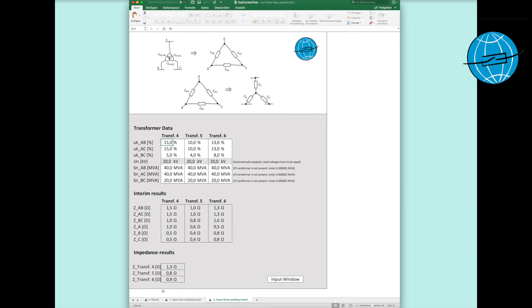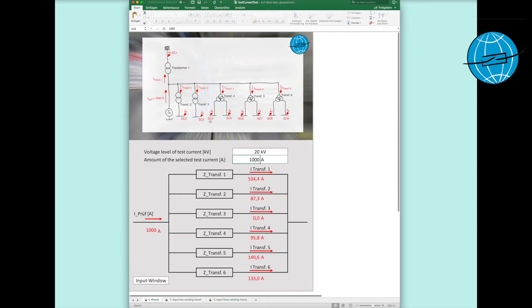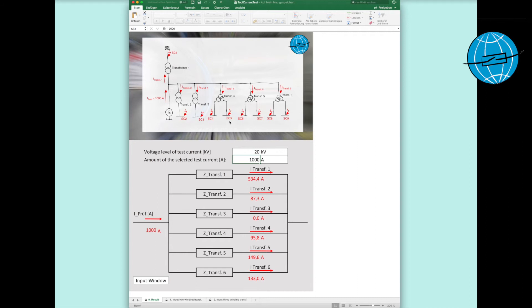In addition, everyone can now convert the results to the under voltage sides of the transformers. For the two-winder and symmetrical three-winder, the transformer ratio is good to go. In case of unbalanced three-winders, the good old current divider rule helps us as always.